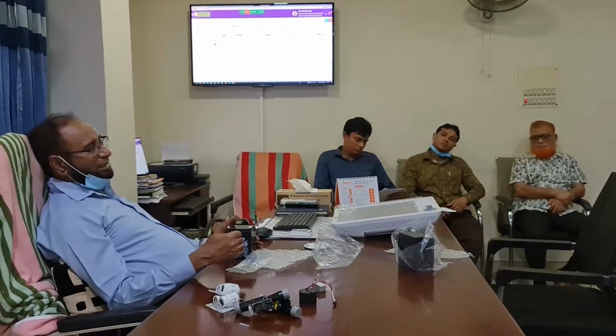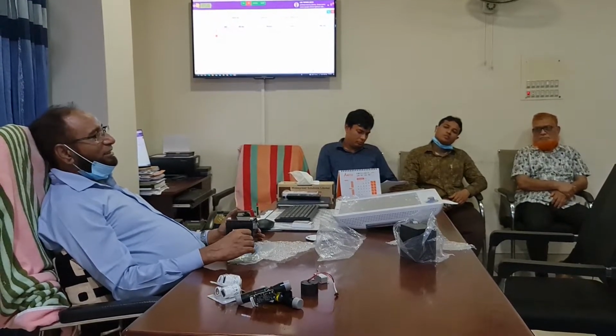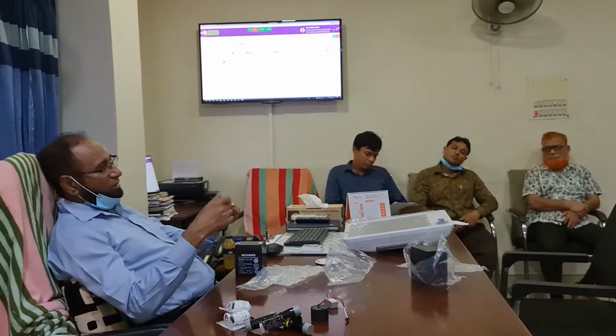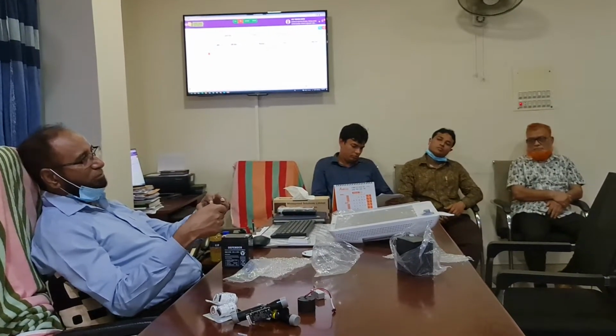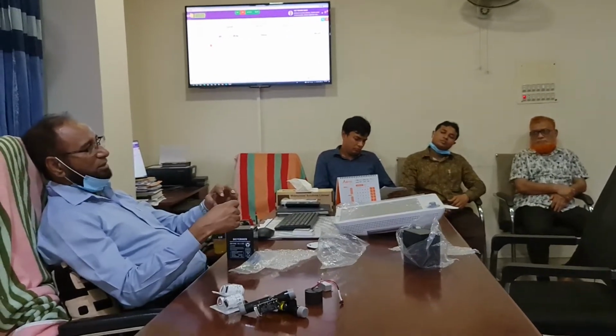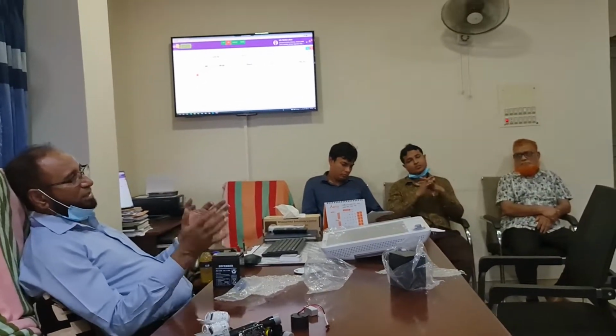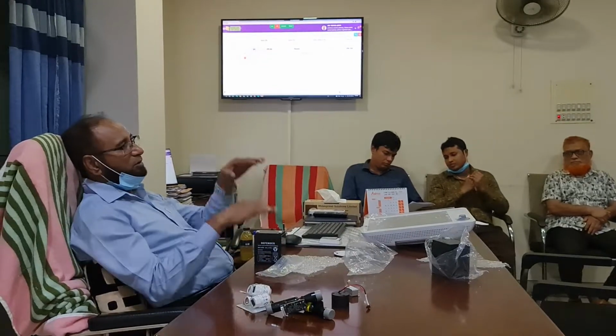This circuit works as a charger and DC power supply. So if you connect AC here, it converts to 24 volt DC and 9 ampere directly, or you can open this and the ventilator can run. But due to fluctuation of the voltage, the parameter setting is affected.